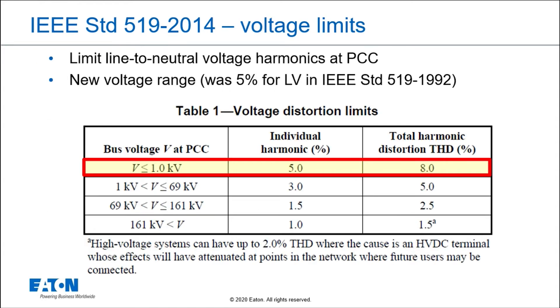Looking at the voltage limit table, you can see it varies based on voltage level: less than 1,000 volts, medium voltage, and high voltage systems. The main change between the 1992 and 2014 standard was that the total harmonic distortion, or THD, in voltage went from 5% to 8%. That was really a function of people understanding that loads weren't typically as affected at a lower level of voltage distortion.